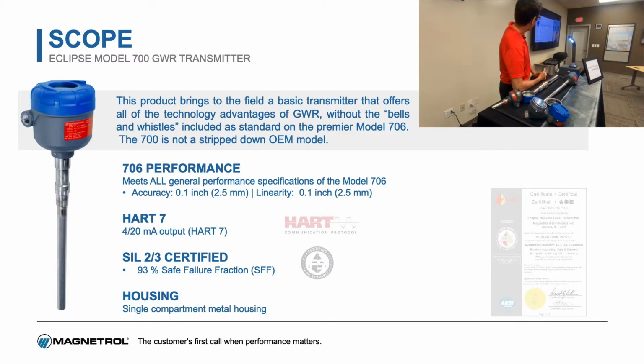It also is a HART 7 device, so it has the latest and greatest HART tools for communication: the DTM, the DDs, the device drivers, everything about it is HART 7 compliant. SIL 2 and SIL 3 certified, with a 93% safe failure fraction. The way we were able to introduce a new product with that safe failure fraction and the SIL 2 certification is that we were able to transport the hours of installation and the months and years of installation experience that we had with the 706, because we designed the 700 on the 706 software and firmware platform.